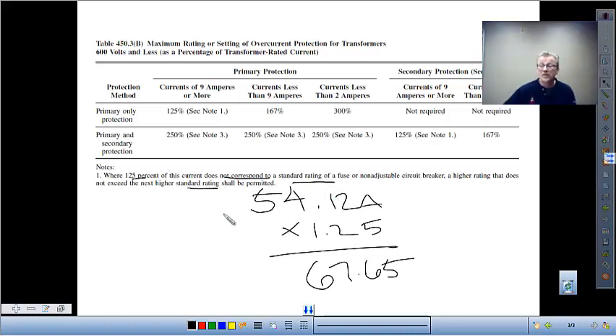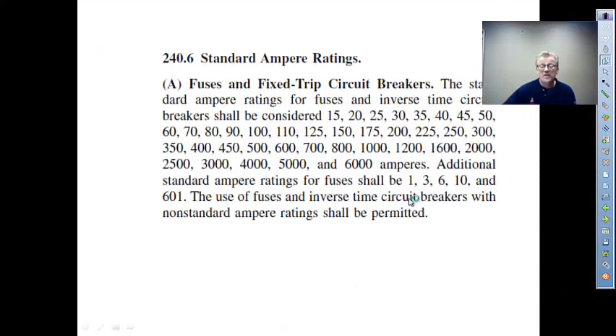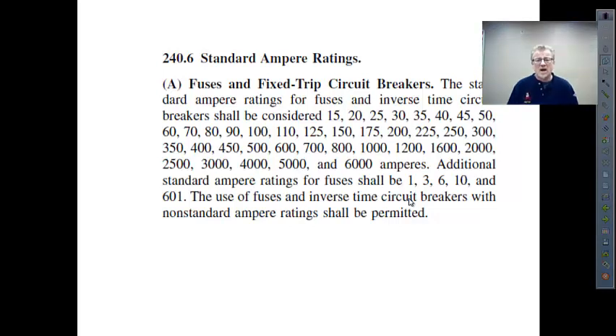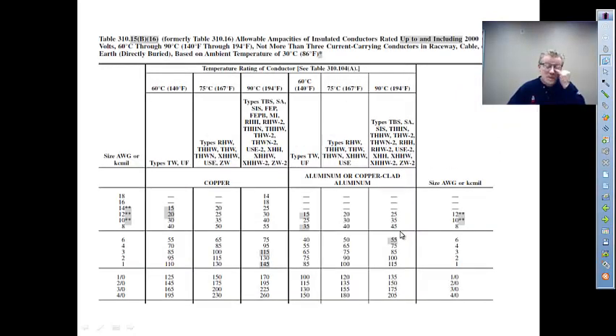So where do we find the standard ratings? We find those right here, 240.6. 240.6 will give us standard ratings of fuses and breakers. 67 is not a standard size, 70 is. We are allowed to protect that transformer. Remember, we're just talking about protecting the transformer now at 70 amps.